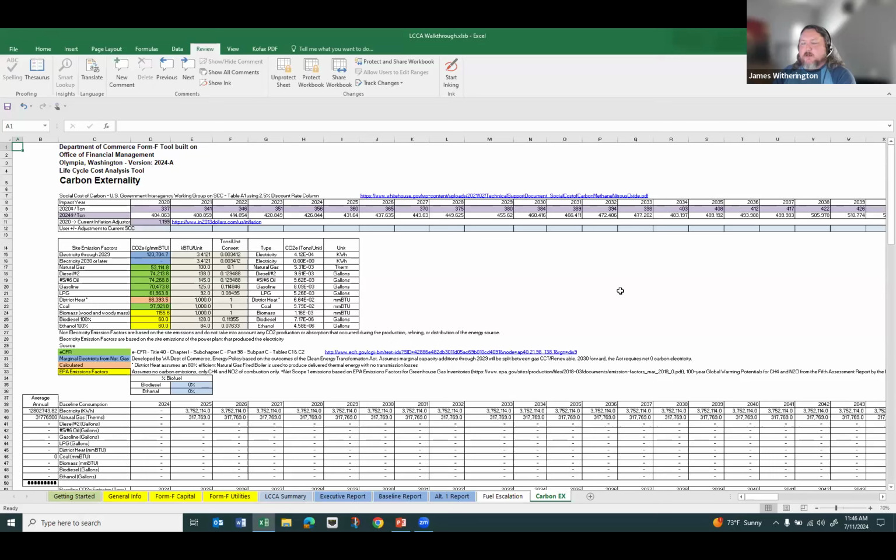Okay. Luke, can I get your thoughts on this, if you don't mind? Yeah, so if no other EEMs pass the simple payback test, and you're going to be implementing the lighting EEM, it makes sense that you wouldn't need to do a life cycle cost analysis, because the life cycle cost analysis is really a tool to eliminate measures from a bundle. So if it's just one EEM and you're not going to be eliminating it, it doesn't seem like you would need to do life cycle cost analysis. But we'll follow up with that question in the published Q&A for this meeting.